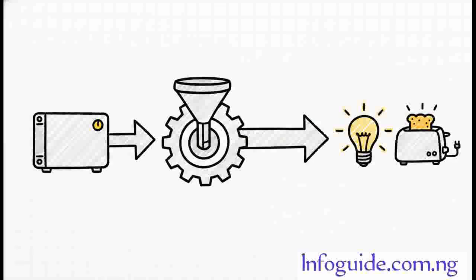So let's look at the math for a second, and don't worry, it's super simple. To find your actual usable power in kilowatts, that's kW, where 1 kilowatt is just 1,000 watts, you simply take your apparent power, the kVA rating, and multiply it by the power factor. So the formula is literally just kW equals kVA times PF.